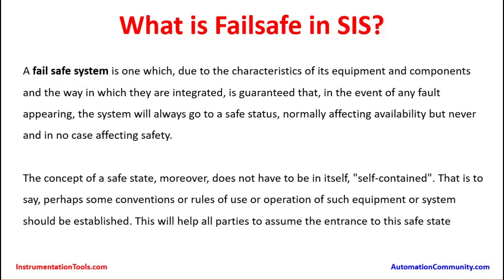What is fail safe in SIS? A fail safe system is one which, due to the characteristics of its equipment and components and the way in which they are integrated, is guaranteed that in the event of any fault appearing, the system will always go to a safe status — normally affecting availability but never affecting safety.